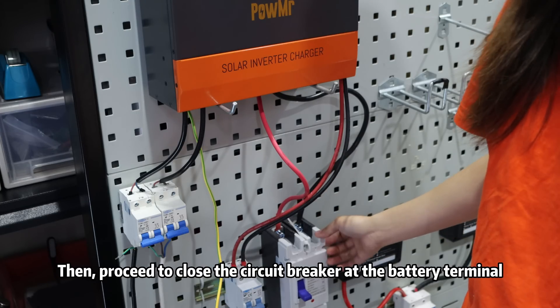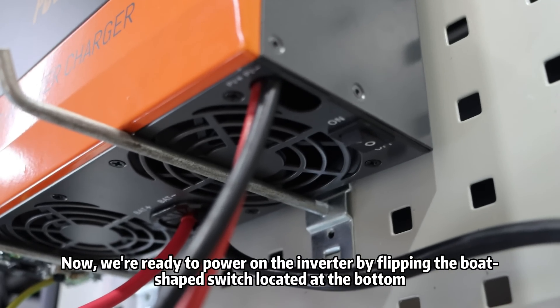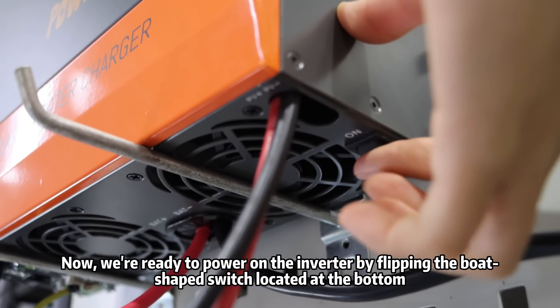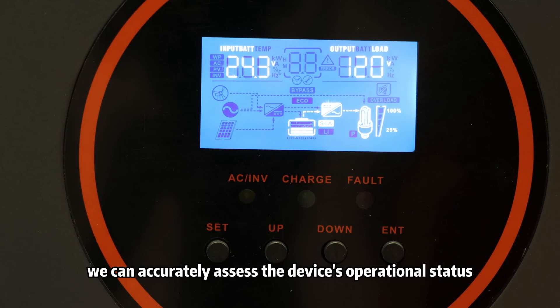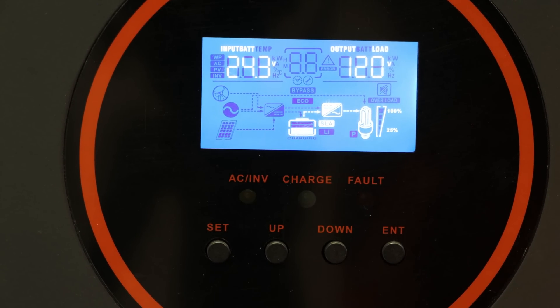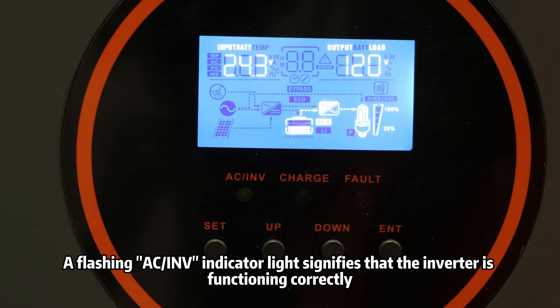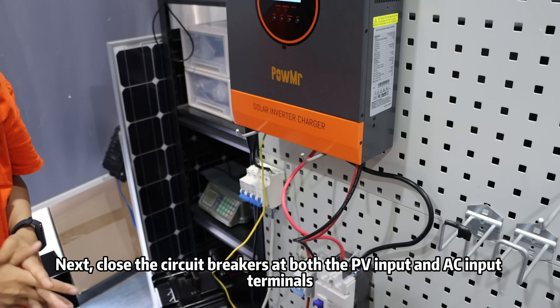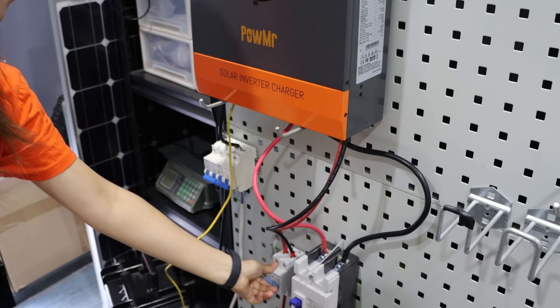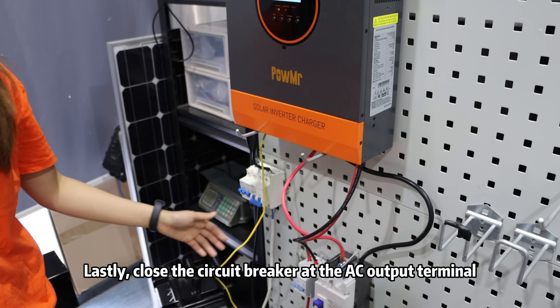Then proceed to close the circuit breaker at the battery terminal. Now we are ready to power on the inverter by flipping the boat-shaped switch located at the bottom. By closely monitoring the indicator lights, we can accurately assess the device operation status. A flashing AC INV indicator light signifies that the inverter is functioning correctly. Next, close the circuit breaker at both PV input and AC input terminals. Lastly, close the circuit breaker at the AC output terminals.